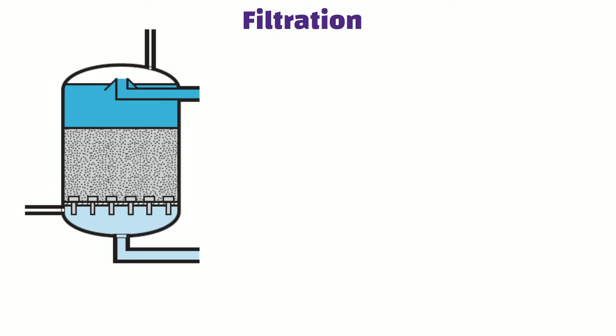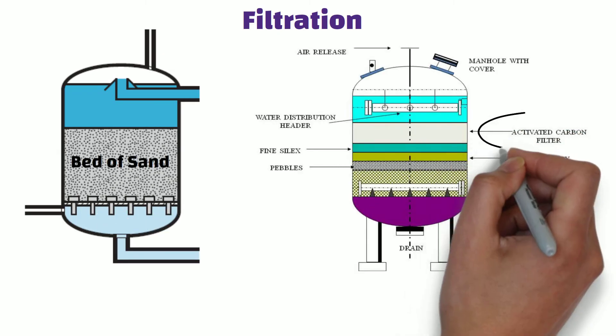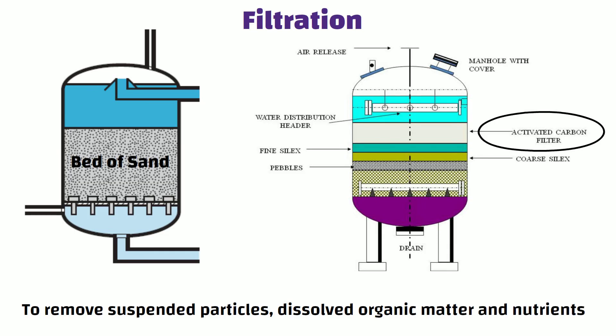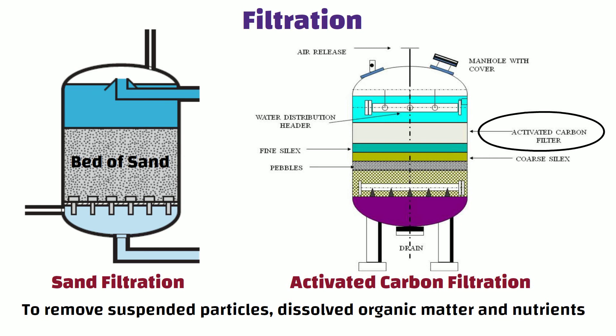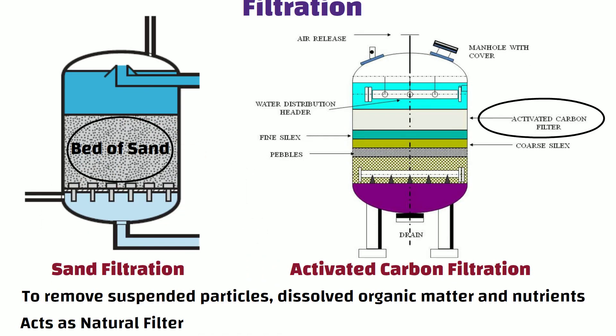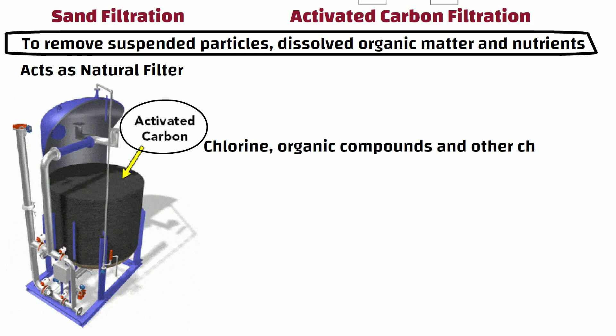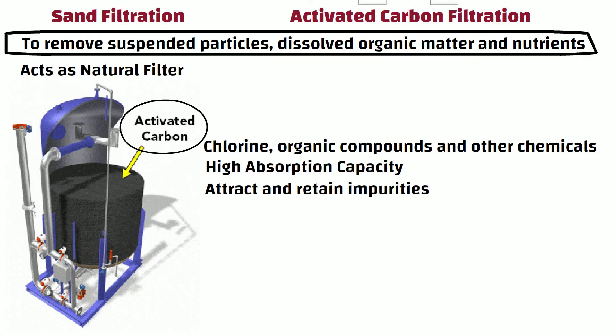The filtration process in STP involves passing waste water through a bed of sand or activated carbon filters to remove any remaining suspended particles, dissolved organic matter and nutrients. There are two types: Sand Filtration, where waste water is passed through a sand bed that traps suspended solids and organic matter, with filtered water collected at the bottom; and Activated Carbon Filtration, where activated carbon filters remove impurities such as chlorine, organic compounds and other chemicals. Activated carbon has a high absorption capacity, enabling it to attract and retain impurities, resulting in purified water.